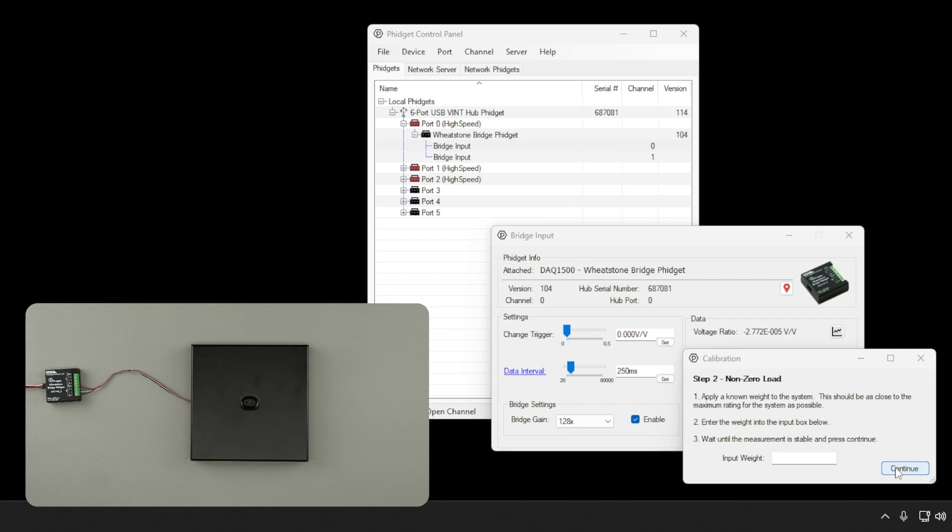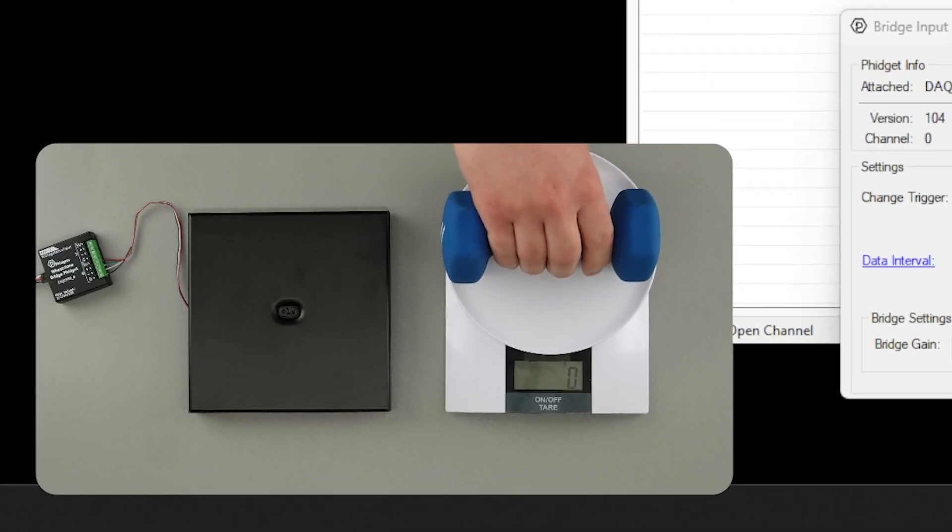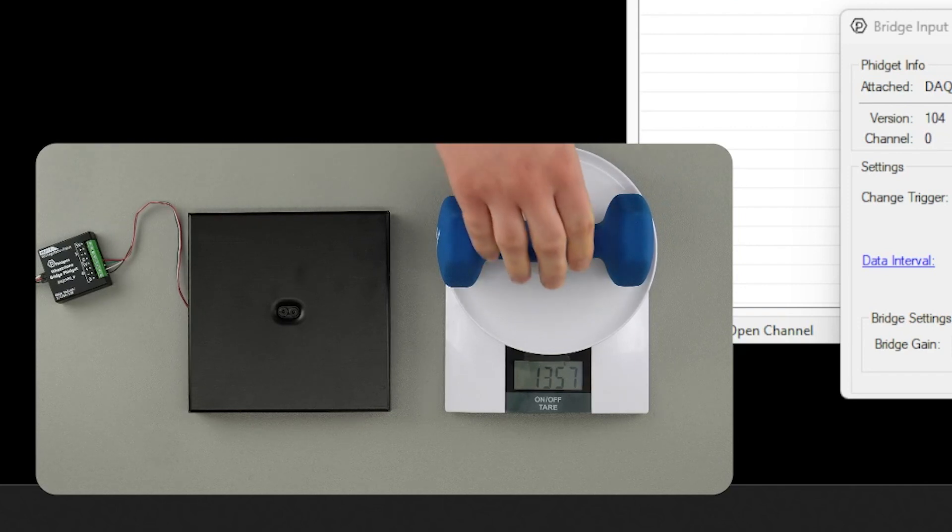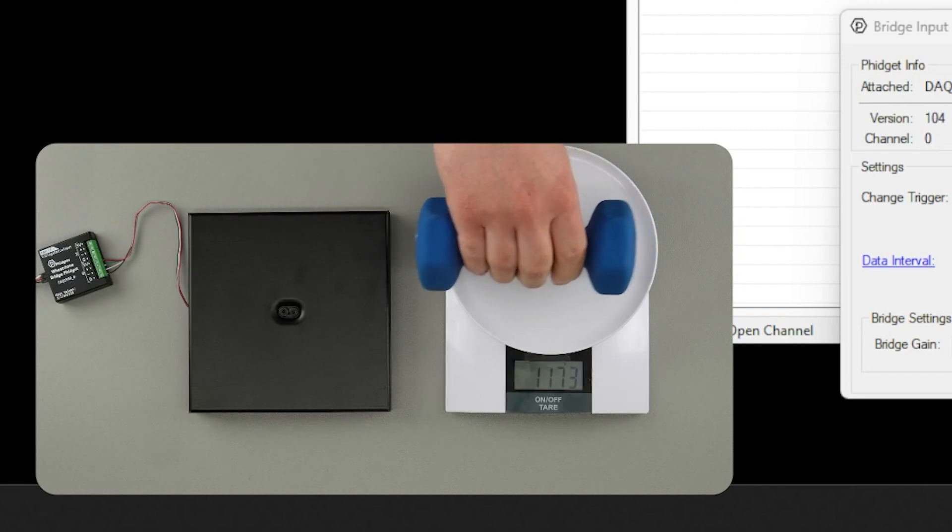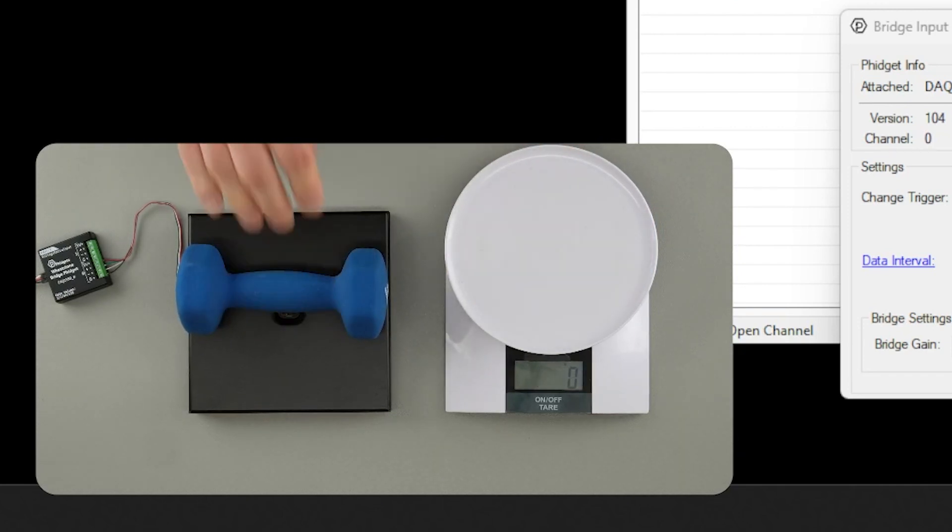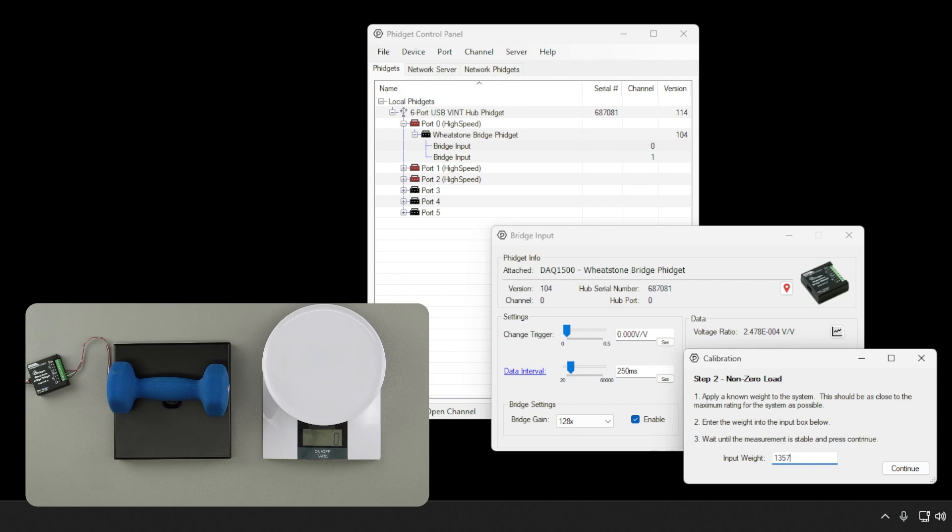The next data point we'll collect is the non-zero load calibration point. In this step, we'll apply a known weight to our system. To start, we'll measure the weight of an object using a trusted scale. We can then load our system with the same weight and enter the known value into the text box. Our weight is in units of grams, so as a result, the output of our calibration will also be in grams.